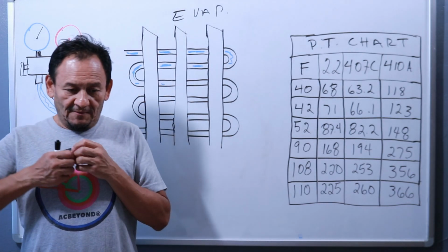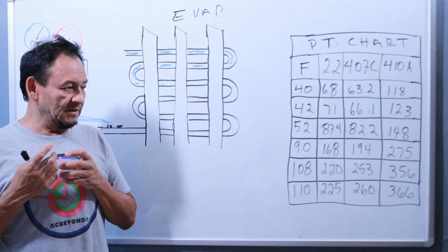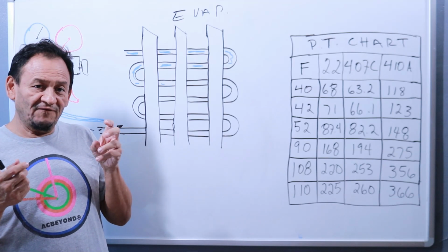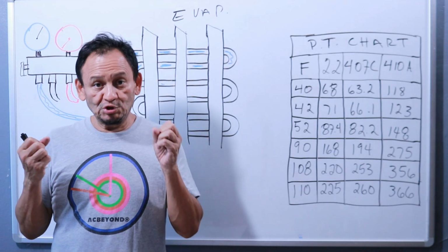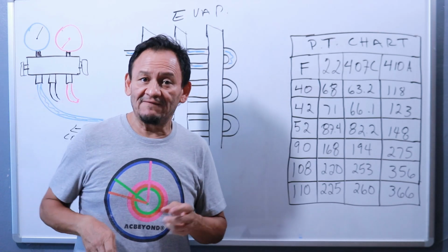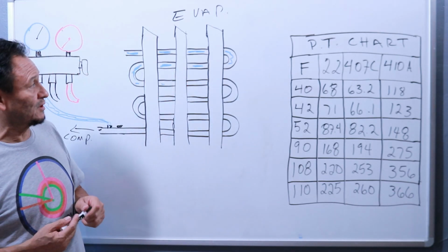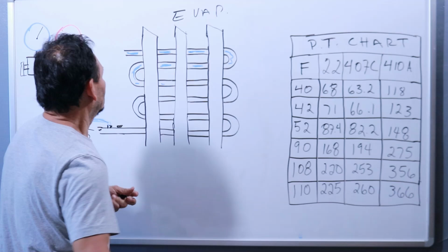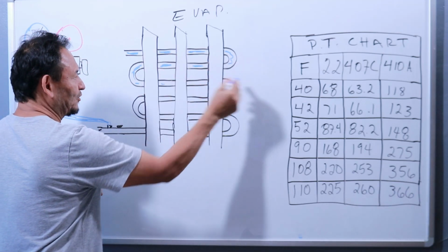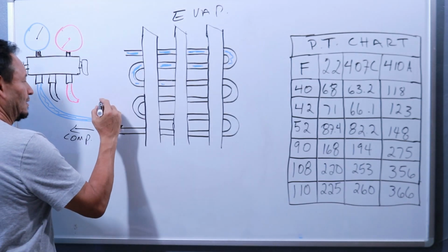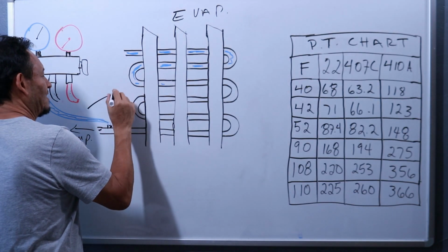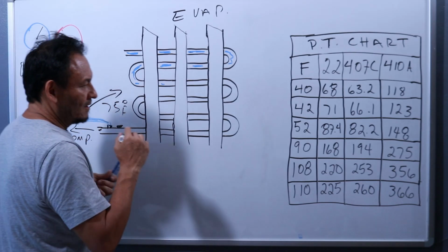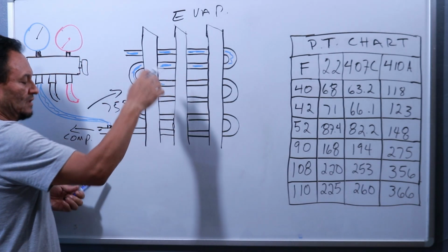What happens in the valve is that 100% liquid comes in, but 25% turns into a mist and cools off, leaving a remaining 75% liquid. So it's cooled off, low pressure, low temperature. It's liquid over here, and as it goes through, it's going to pick up heat. If you have air coming in at 75 degrees Fahrenheit, that's the heat you're adding into the evaporator.